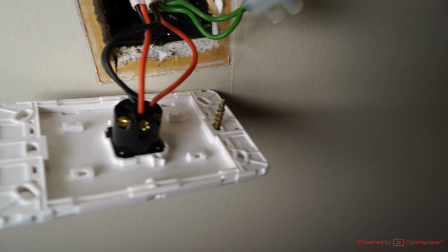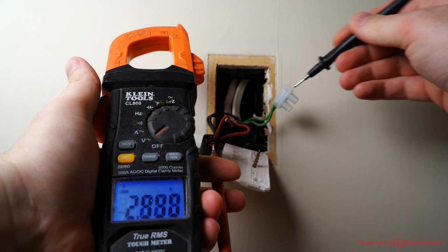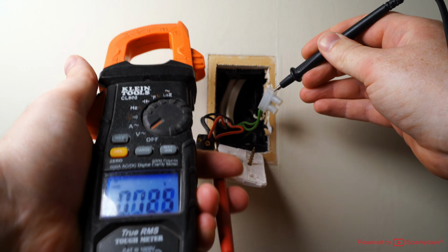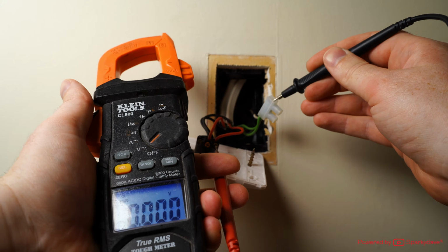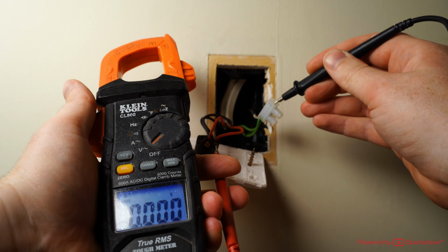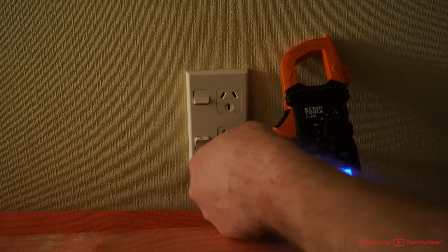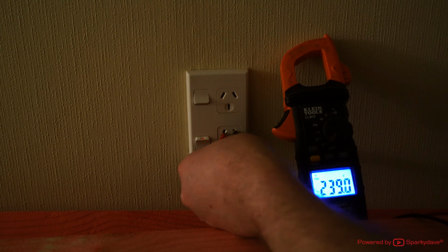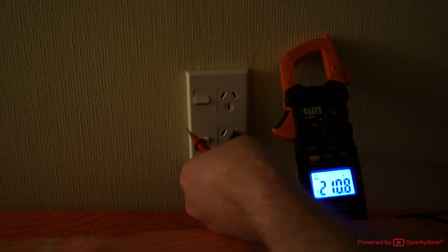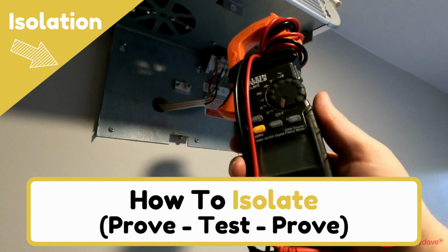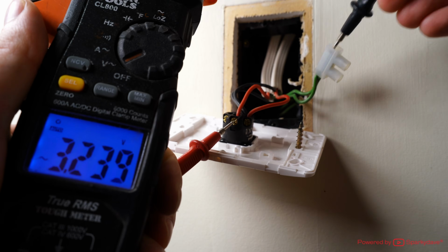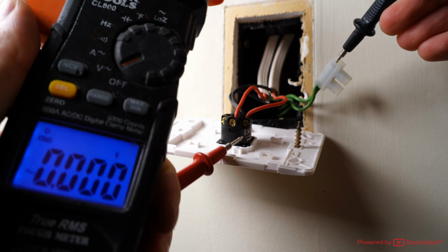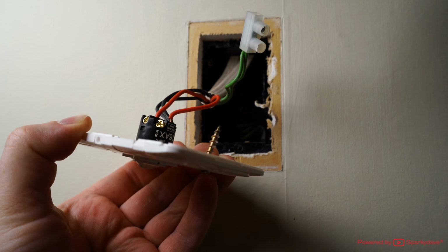After this, test behind the light switch between each red phase cable and the earth if available, or neutral cable. The multimeter should display 0 volts. Following a reading of 0 volts, check to ensure the multimeter is still capable of testing for 230 volts by using the multimeter with the same known live power source as used earlier, and ensure 230 volts is displayed. The prove-test-prove method is how we can verify a circuit is dead. When verified that no voltage is present at the light switch terminals, it is safe to remove the cables.